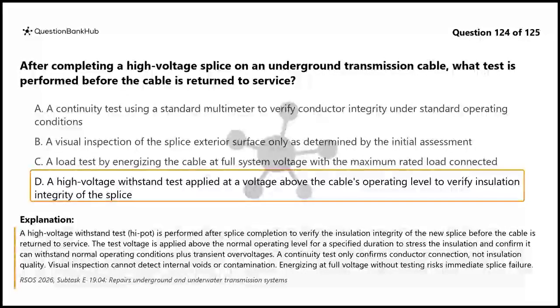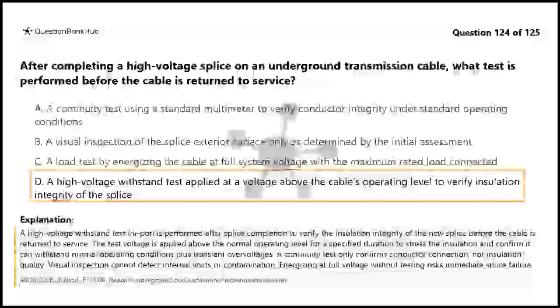A high voltage withstand test, HIPOT, is performed after splice completion to verify the insulation integrity of the new splice before the cable is returned to service. The test voltage is applied above the normal operating level for a specified duration to stress the insulation and confirm it can withstand normal operating conditions plus transient overvoltages. A continuity test only confirms conductor connection, not insulation quality. Visual inspection cannot detect internal voids or contamination. Energizing at full voltage without testing risks immediate splice failure.